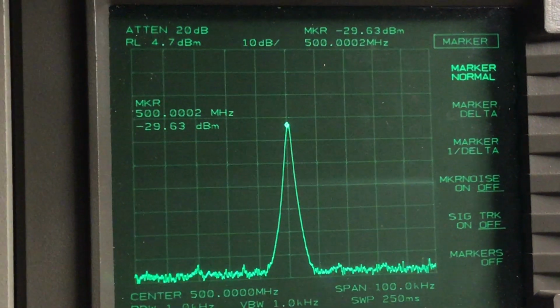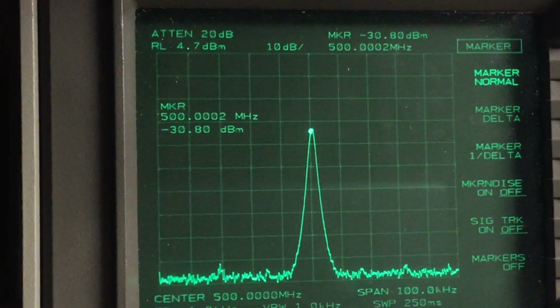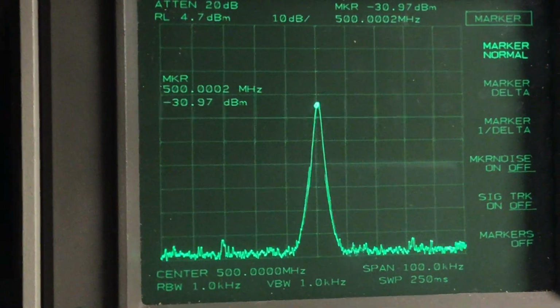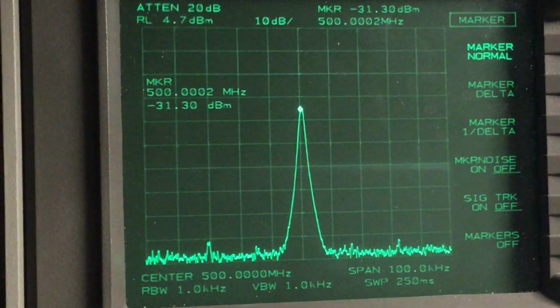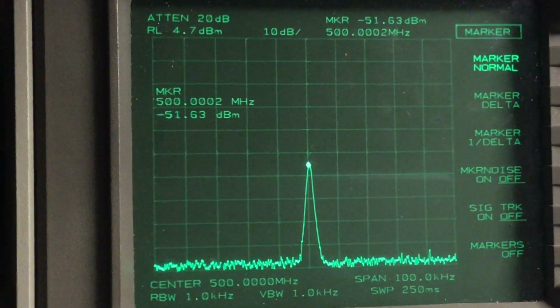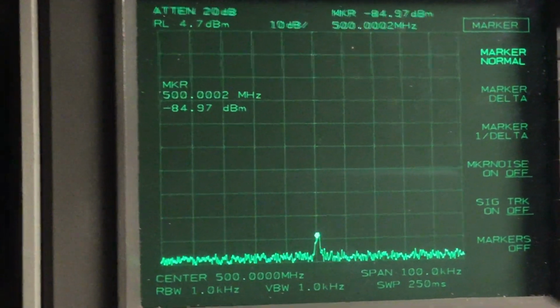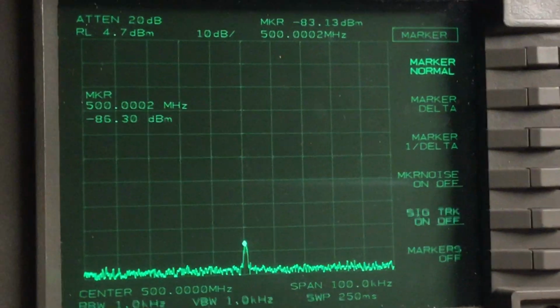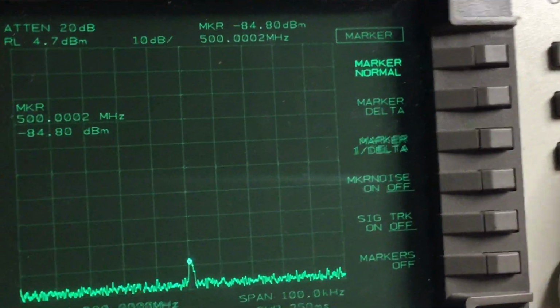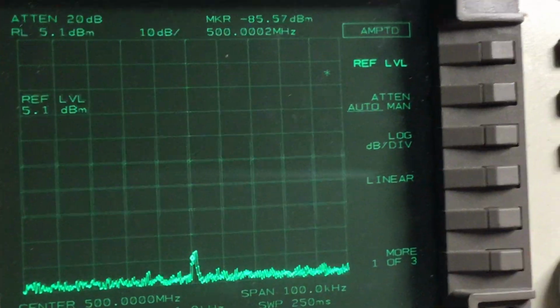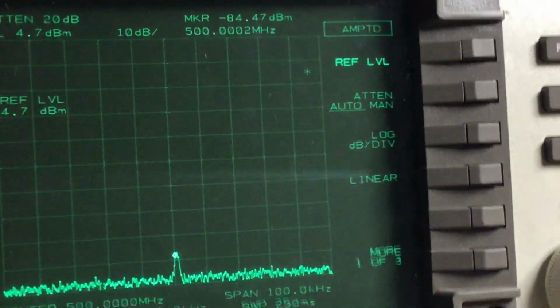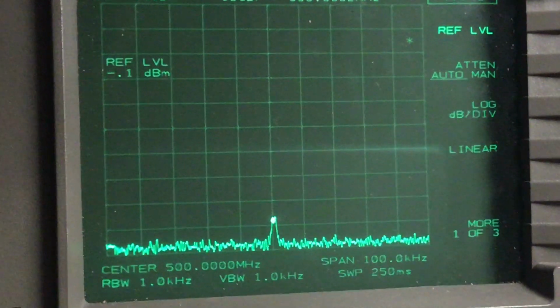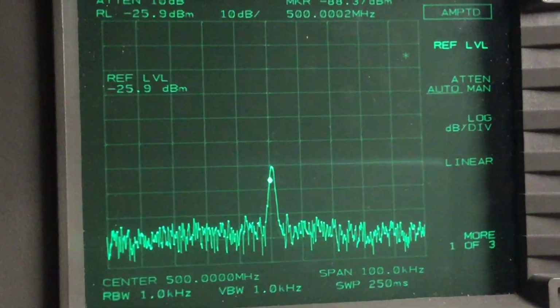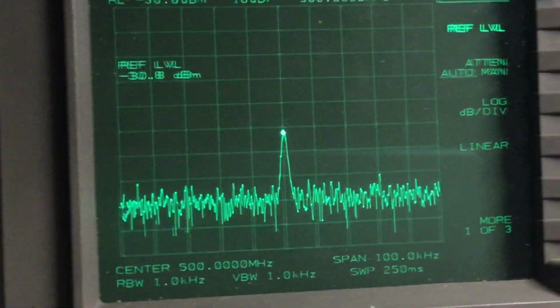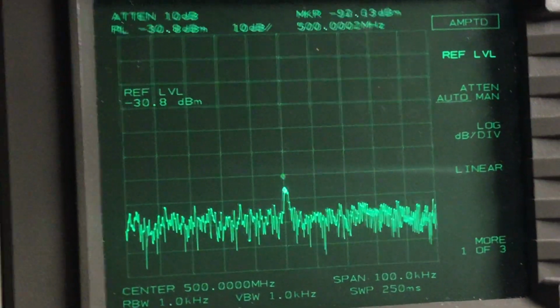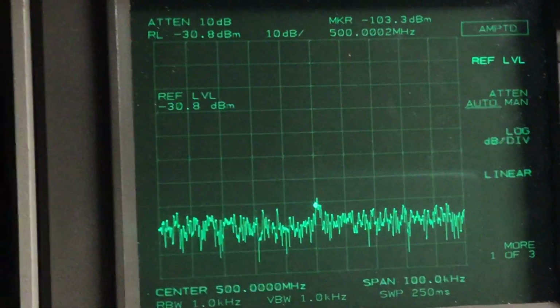So it's neg 30 dBm, which in microvolts is 7.02 millivolts, and then we can keep going down in the dBm scale and really get into what would be the noise level. So it's neg 83 dBm. We'll need to then adjust the amplitude on the spectrum analyzer as well. So we'll get that up to noise floor's picking up now. And so we're down now almost into the noise floor of the thing.